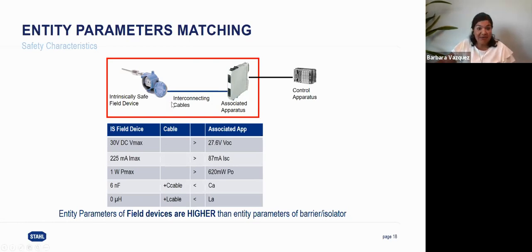And what about the cable? We say the cable is part of the system, and the cable will store energy. So we do need to make a calculation to make sure that we don't have too much cable that can store energy that could create a spark hot enough to react. For that, we need the capacitance and the inductance, and we need to do the calculation, again, to make sure we don't have too much energy. So cable length is important.